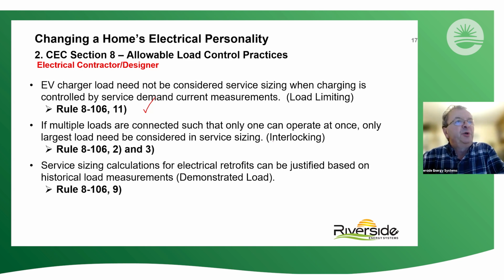Secondly, there's this principle that is referred to as interlocking, which is basically making it impossible for more than one load to run at a time and put loads on a common circuit. So for example, if we can put a couple of loads on the same circuit and interlock them using a device such that only one can run at a time, then Rule 8-106, 2 and 3 tell us that we only have to consider the largest of the two. So this is another benefit.